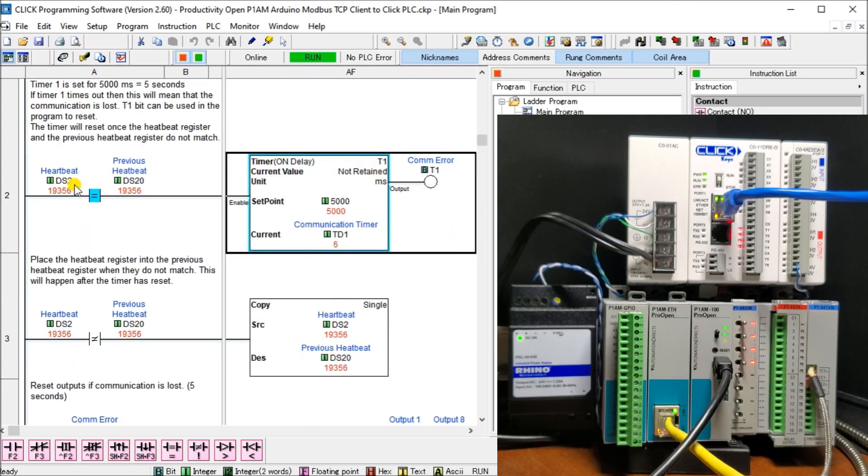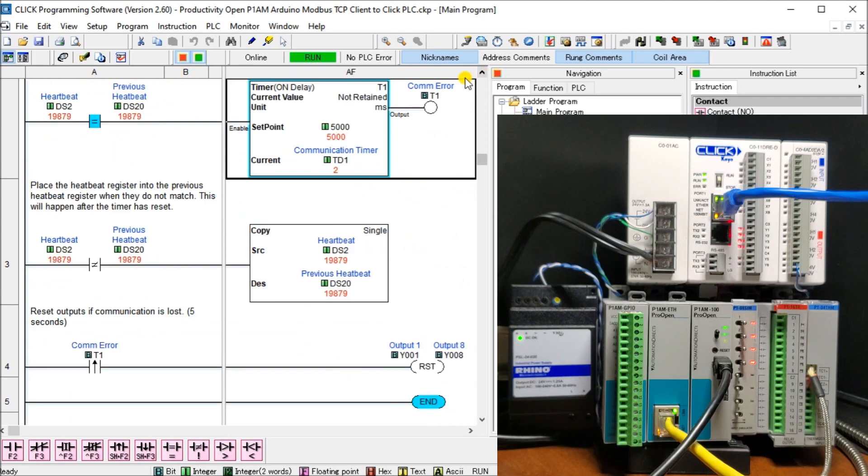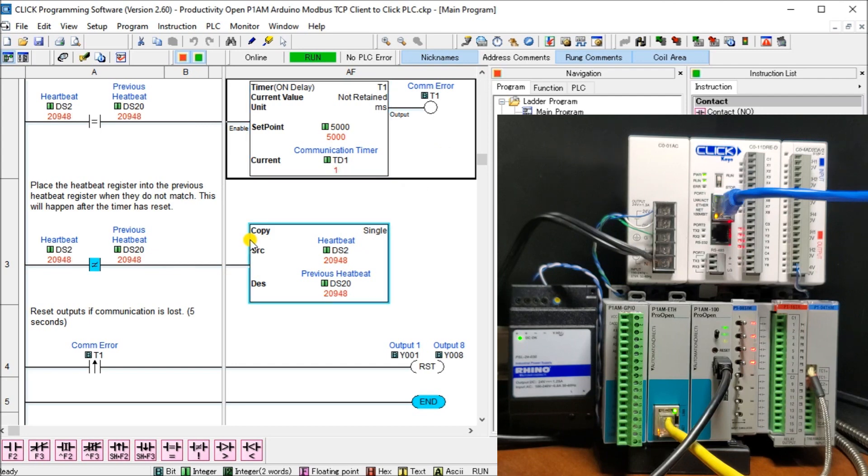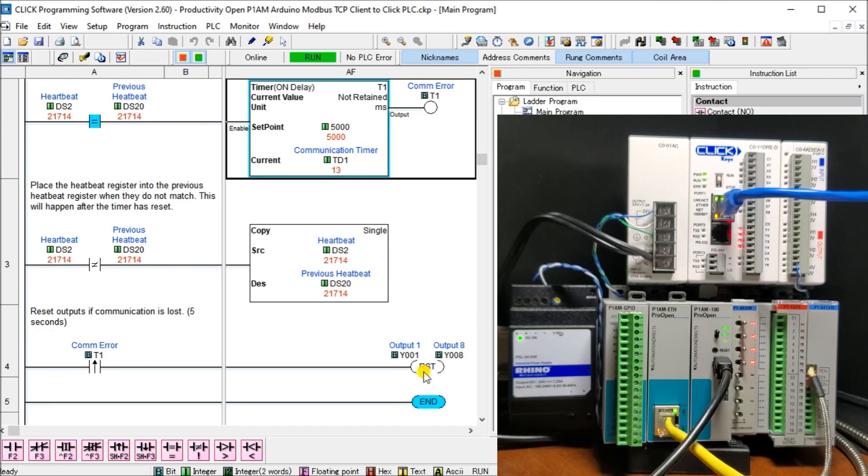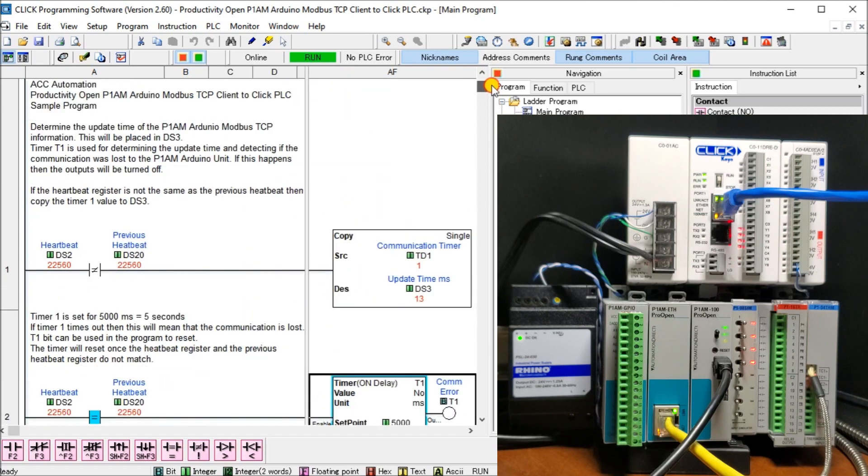Then what we do here is if they're not the same, then we move our heartbeat into our previous one. So that's our order of sequence. So we set our time, once they're different, then we reset our timer and then we reset our heartbeat previous time. So that's how we determine, first of all, if we're running and how fast we are updating from our slave unit. Then what we do is if communications is lost, we said that we have this comm time one, it will actually time out when it does, it will reset all of my outputs. So back to zero again. So I know the state of it if I lose communication.